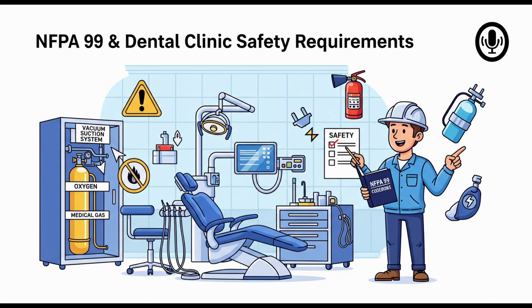Okay. Now, what about the piping itself? Getting the air or vacuum from the source to the treatment rooms. You mentioned sections 15.4.4 to 15.4.9 and 5.1.10. Sounds like there are specific rules there too. Oh, definitely. This is where it gets really technical. Section 5.1.10, applied via 5.3 for Category 3, dictates the materials and how you join them. For copper pipe, which is common, you can't just use standard plumbing copper. It has to be medical gas tubing, typically type K or L, that's been specially cleaned by the manufacturer to remove oils and contaminants. It will have markings on it like OXY or MED or VAC-C, often color-coded too.